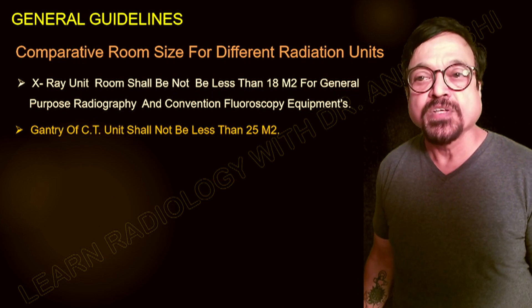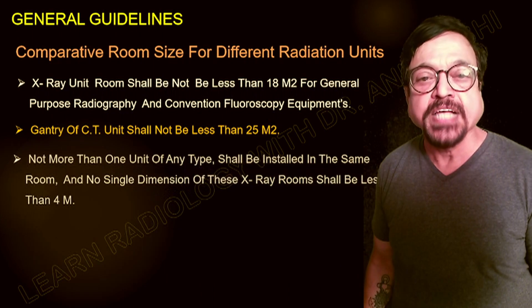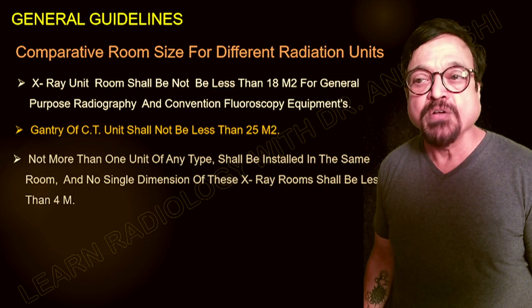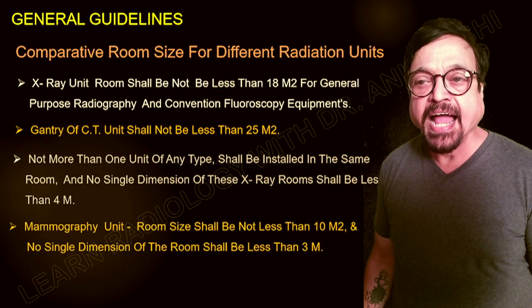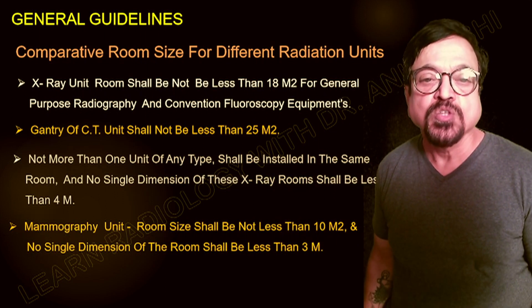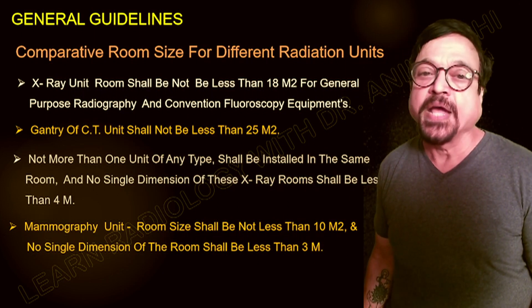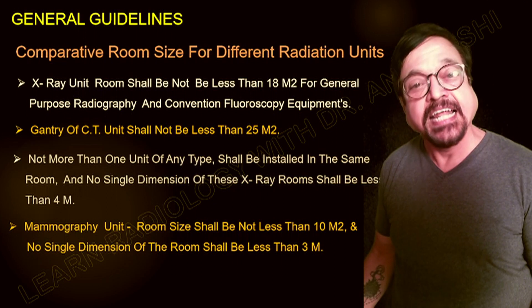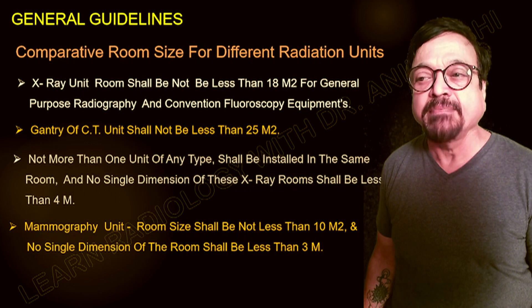For CT, the gantry room has a different scale — it is 25 square meters — because it uses high-radiation x-rays for longer time periods. Not more than one unit of any type shall be installed in the same room, and no single dimension of these x-ray rooms shall be less than 4 meters. You cannot install two x-ray units or two radiation-generating units in the same room.